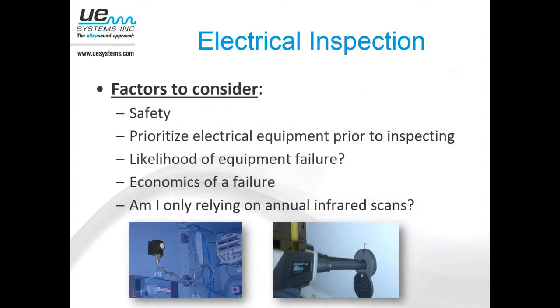Some things to think about with electrical inspection. Obviously, safety is a real big one. Obviously prioritizing which equipment you need to go out to, and the way to do that is how likely is it to fail, the economics of a failure, and are you relying only on an annual infrared scan? I know many plants or companies use insurance companies to come out once a year and do infrared scans, but in between those inspections, what are you doing to ensure that your workers are safe and that you're not risking some type of electrical catastrophe?